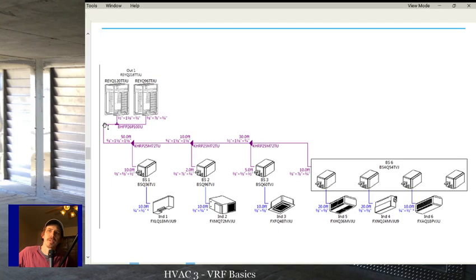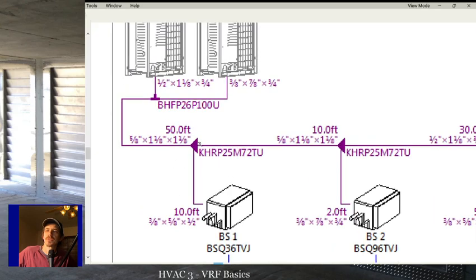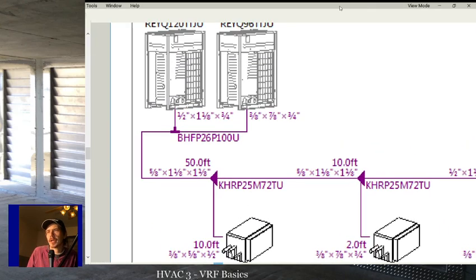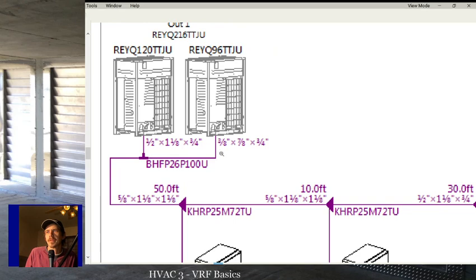and then the smallest ones follow commands from that outdoor unit, right? Then you'll have the three line sets that go down, and I'll zoom in a little bit here. And you'll see on this particular diagram, right, half inch by an inch and an eighth by 3/4 comes out of this unit. This would be a 10-ton unit. 3/8 by 7/8 by 3/4 comes out of this unit. That is an 8-ton unit.